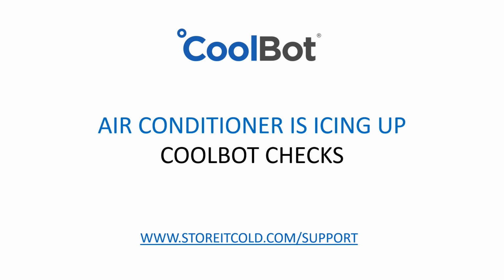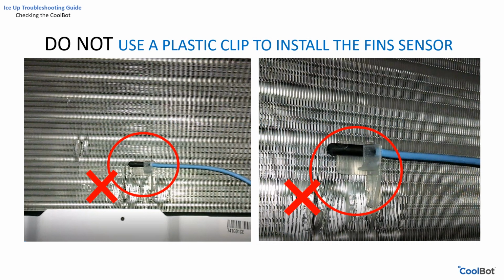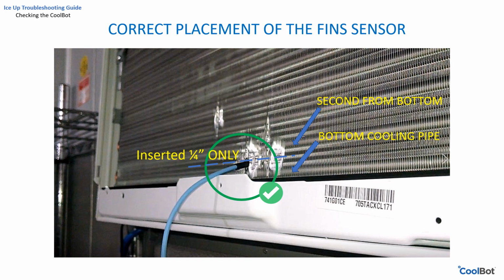Let's get started with the CoolBot checks. Is your fin sensor correctly positioned? Make sure that the fin sensor is not installed in a plastic clip in front of the fins of the air conditioner. The fin sensor tip must be touching the fins of the air conditioner. The fin sensor should be only 1/4 inch deep between the lowest and second from lowest horizontal cooling pipes. Make sure that the sensor is touching only the fins and not touching the cooling pipes.